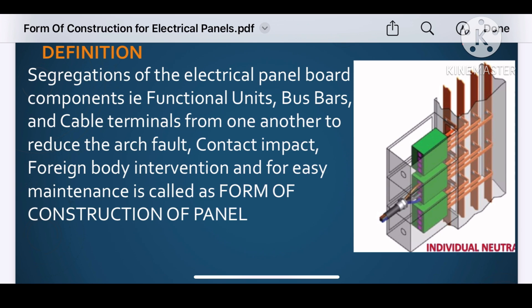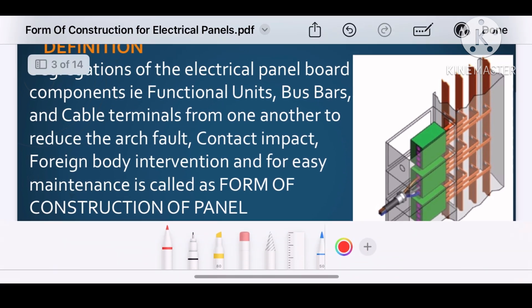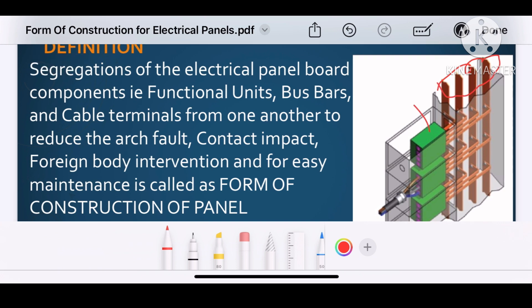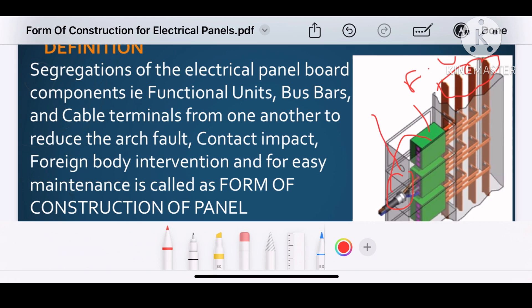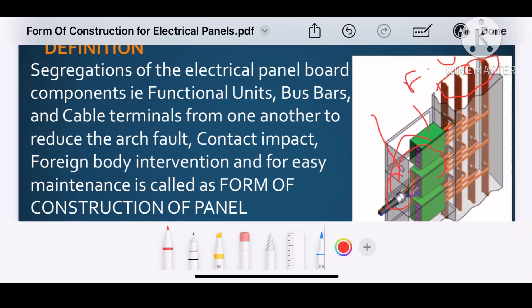It means that the form of construction is defined as the segregation between bus bar to functional unit, and functional unit to the cable termination. Based on the degree of separation between bus bar to functional unit, functional unit to functional unit, and functional unit to termination, the form of construction is defined — as form 1, form 2, form 3, or form 4 construction.